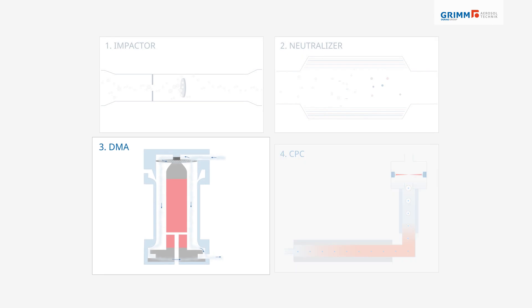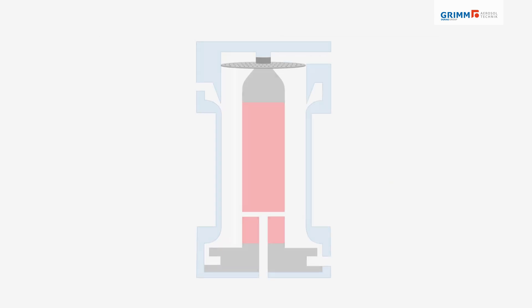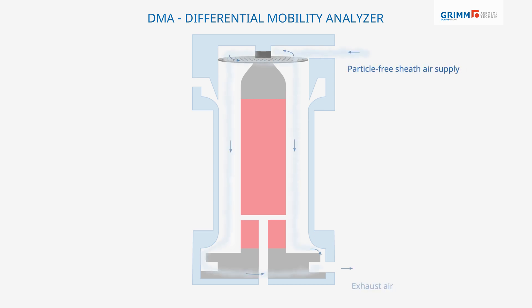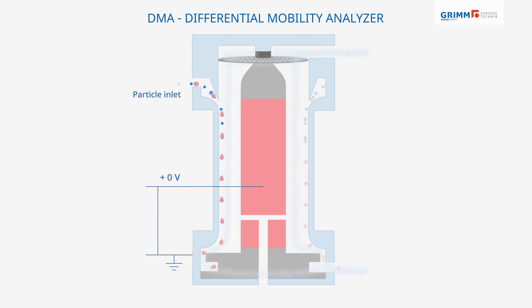The Vienna-type DMA classifies particles into size bins. Particle-free sheath air circulates between two cylindrical electrodes. This laminar sheath airflow prevents particles from reaching the center electrode when no voltage is applied.